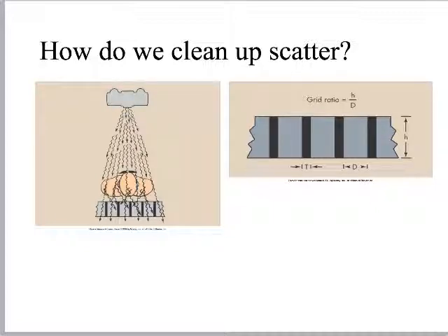But for digital, you can use the grid perfectly well and still wind up with an artifact. This is especially true for computed radiography. So what's happening? Well, you may remember our brief conversation about the Nyquist theorem, that we have to be sampling twice in order to have a good image, right? We have to sample twice for any one pixel. With grids, though, we've cut off our sample, right? We've decreased our sample size. And so we can start to affect that Nyquist theorem.